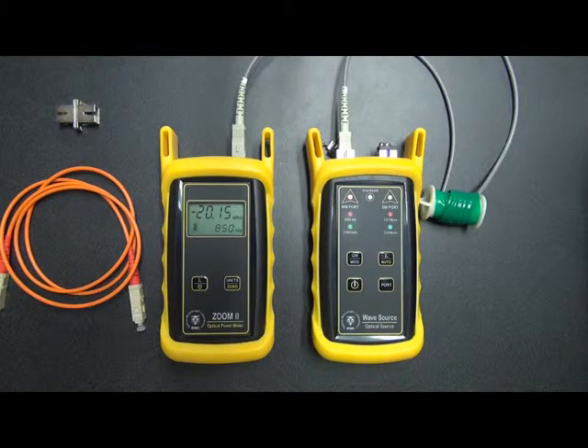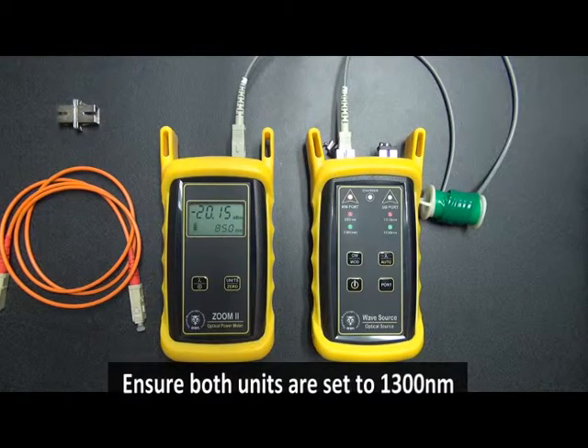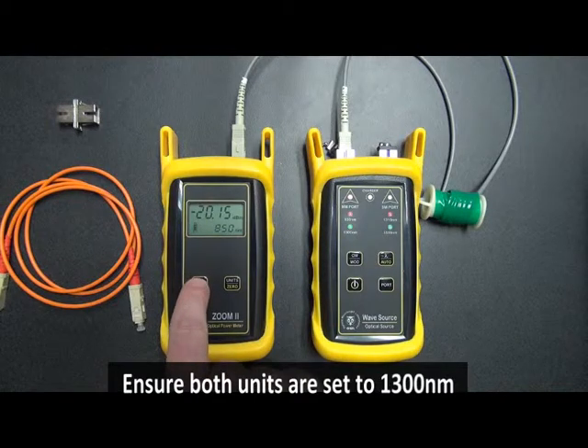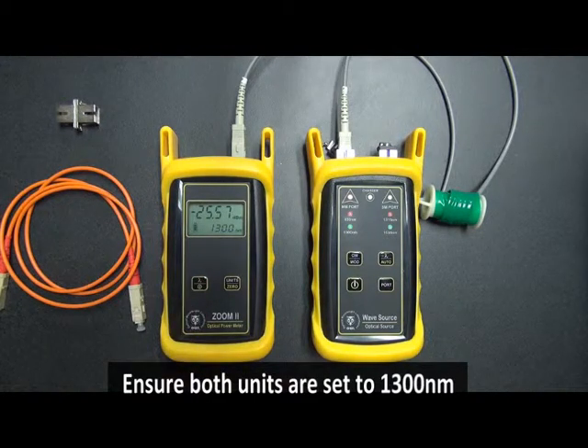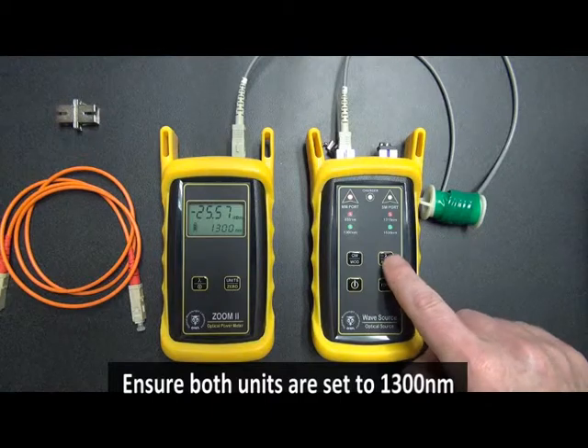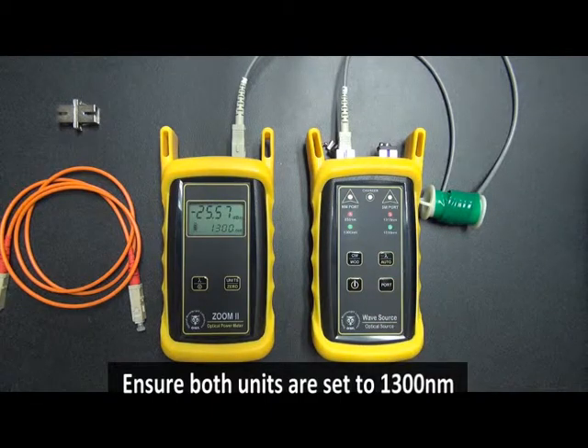The second thing we want to do now, if we're doing a dual wavelength measurement, is to make sure that 1300 is also at a proper power level. So we press the wavelength button until we see 1300 on the Zoom, and then we press the wavelength button on the WaveSource to switch to 1300.